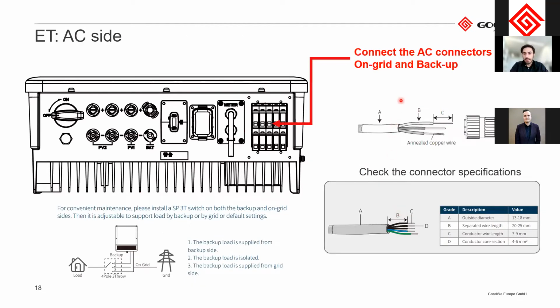When all of this is done, then you just connect the AC connection here on this one. There is a cover afterwards that you need to pull the connector through, and then connect this, and then you put the cover on the inverter. Also for the backup switch here, it is recommended to install the SP3T switch on both the backup and on-grid sides.